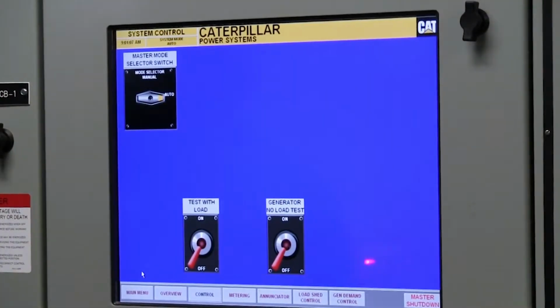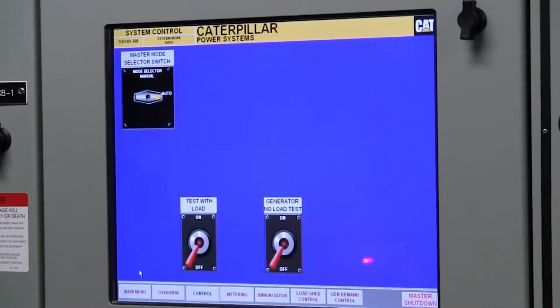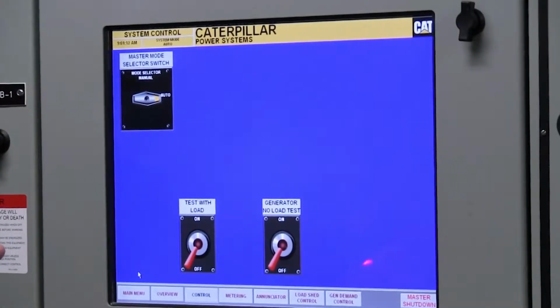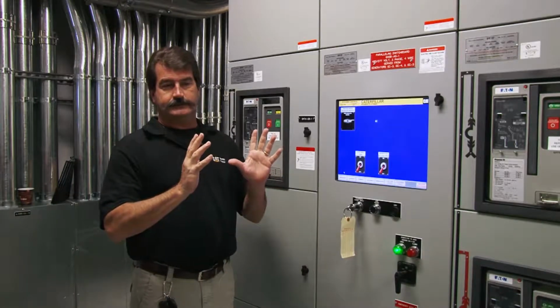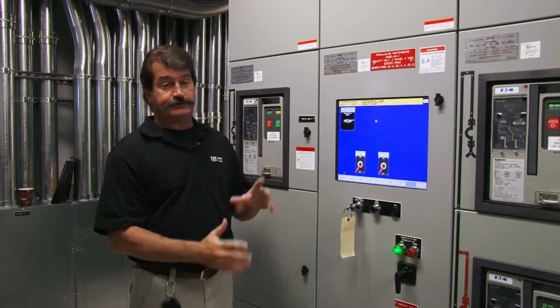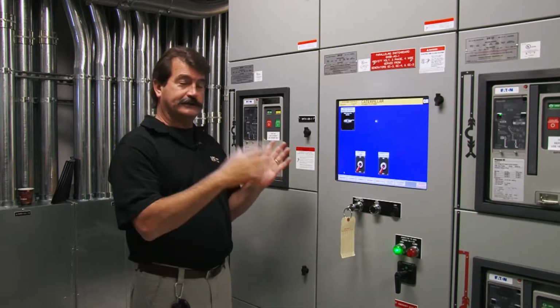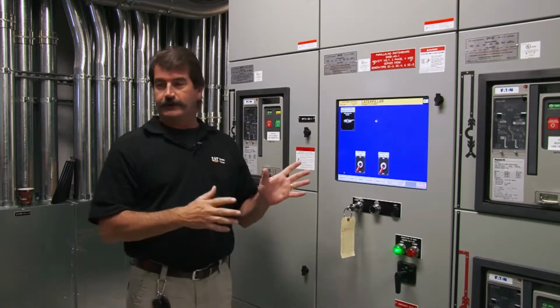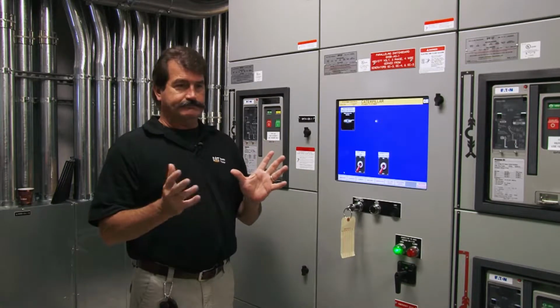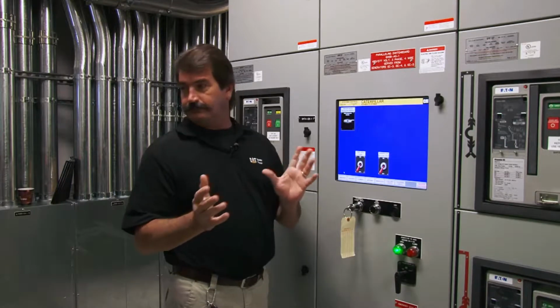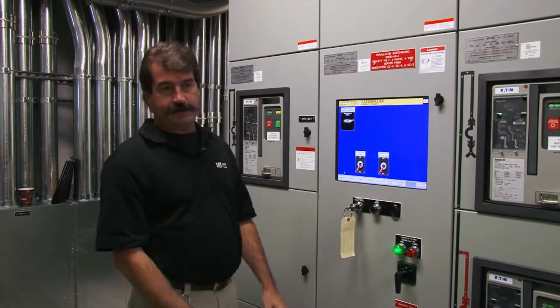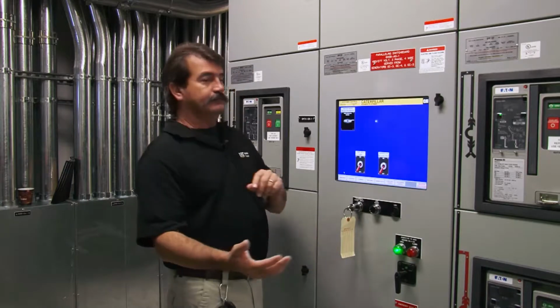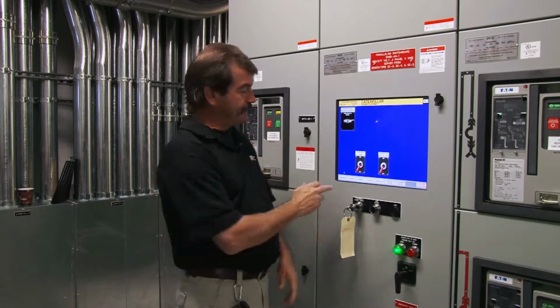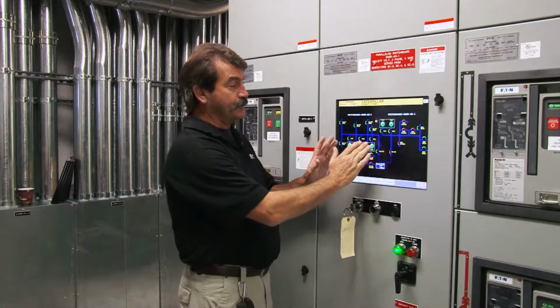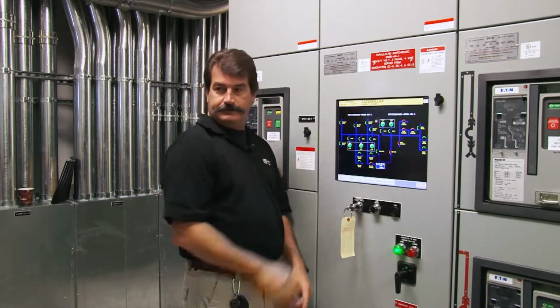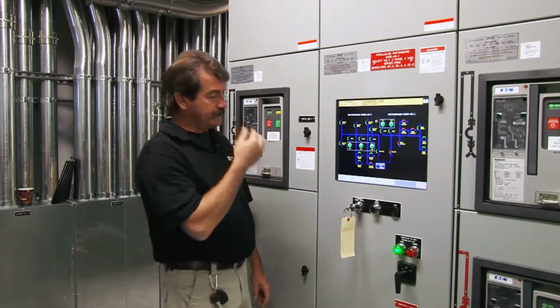Go to system control here. We'll have a timer come up — it's not a retransfer timer since you're not doing anything, but as soon as the last ATSs have moved over, it'll run for another five minutes or so, I'm not sure exactly what it's programmed for, and then you're good to go. Once the gen breaker pops open, you'll start opening these other breakers too.